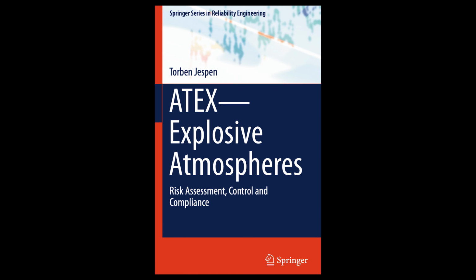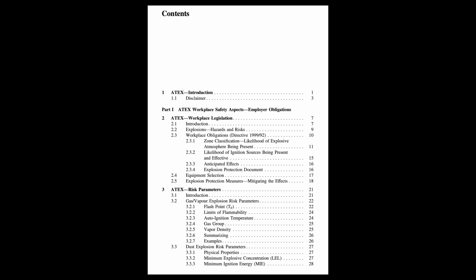Okay, the official stamps. Then the core technical info, the equipment group, I for mining, II for surface industries, and category 1, 2, or 3. An indication of suitability for gas, G, or dust, D, the type of protection used, like Ex d, the Ex codes. Yes. And critically, the temperature class, T1 to T6, or the actual maximum surface temperature in degrees C. For Group II equipment, sometimes the gas group, IIA, IIB, or IIC it's suitable for, is also marked.